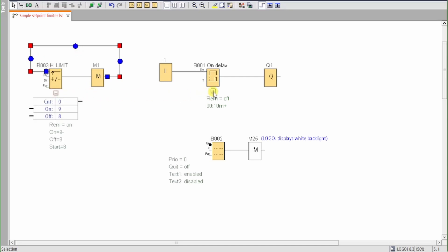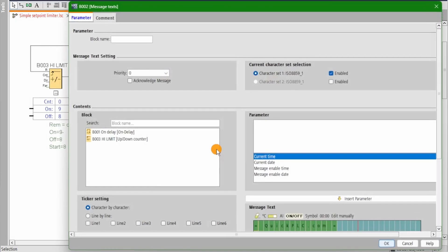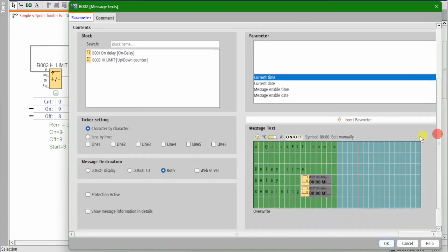Expand the parameter display on both blocks and create a reference from the counter's count value to the timer's T value. Next we'll go to the text message and we'll delete the timer's on delay parameter and replace it with the counter's count value, which is what the user will edit.